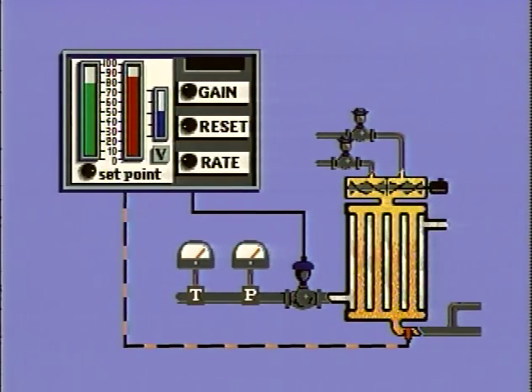The PID controller could maintain the temperature at plus or minus 5 degrees, but the delay in the transfer of heat prevented it from controlling the temperature more precisely. What was needed was a new way of controlling the temperature, a way that could respond more quickly to changes in the conditions that cause changes in the product temperature. This meant finding disturbance variables in the production system that quickly reflected these changes. This turned out to be the shell pressure in the heat exchanger.